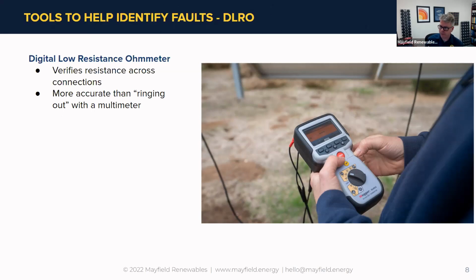The interesting part for me is the IEC standard I keep referring to talks about doing a continuity check. It's just a 2-sentence part of that standard that really just says you need to do it. There's no spec to it, no pass-fail number or anything like that. This gets back to setting that baseline, taking the reading when you're commissioning, knowing what that value is, and watching it over time, making sure the low impedance path you're expecting for ground connections isn't showing high resistance. That's one of the tests I think should be incorporated.